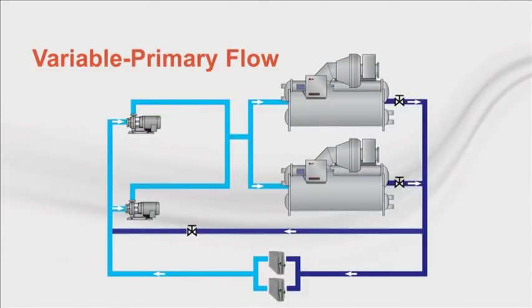All right, let's move on to the next configuration, variable primary flow. Since the mid-1990s to early 2000s, variable primary flow systems have become quite popular. It was we chiller manufacturers who insisted on constant flow. Now that chillers have more sophisticated controls, we can allow varying the flow through them. In this system, we have at least one chiller, at least one pump, and a minimum flow bypass. Here you see a 2-chiller VPF system with 2 manifolded pumps and a minimum flow bypass sized for the minimum flow of the largest chiller.